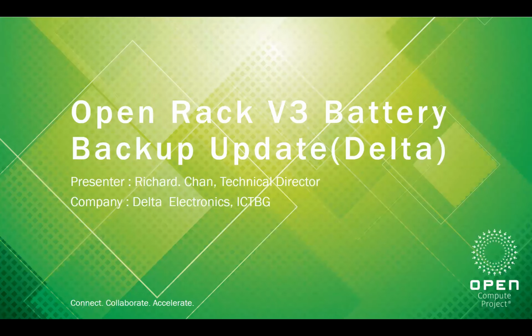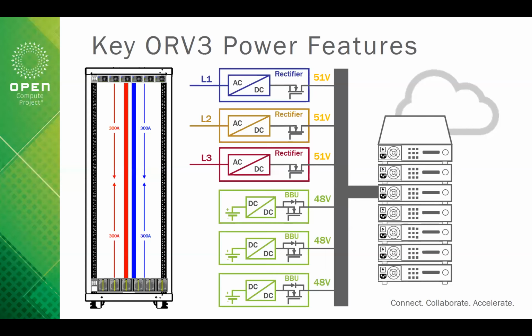I would like to introduce our current Open Rack V3 BBU product development status. As we know, the ORV3 is a 48-volt power distribution system. It has a 51 volt power shelf output and a 48 volt BBU shelf output. The power shelf has 3-phase input, and we can use 6 or 3 power supplies to do output current sharing to achieve input current balance. Also, the BBU provides a backup function to maintain the output demand from the IT device.